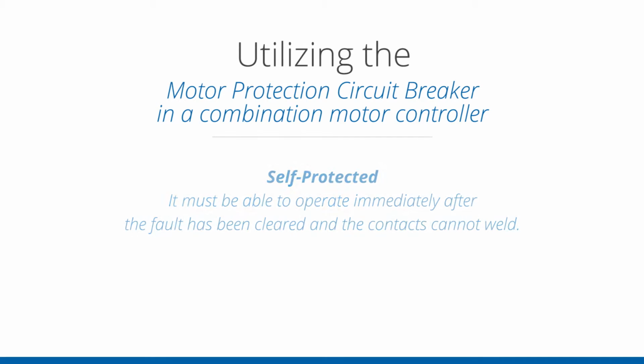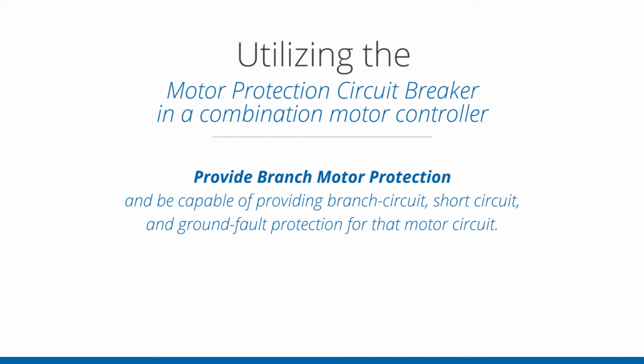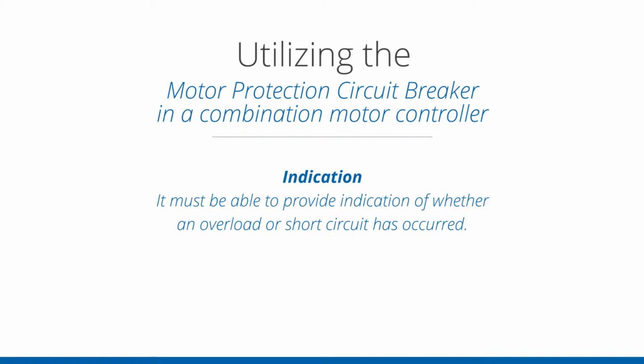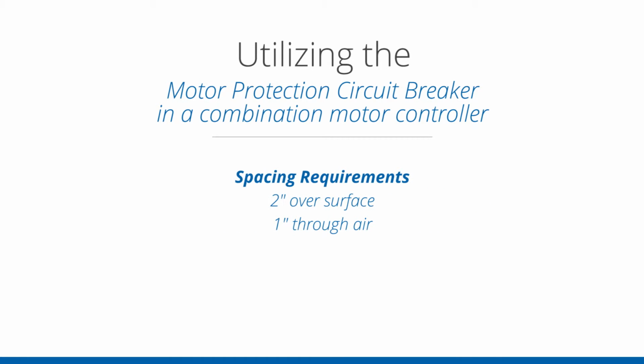First and foremost, it must be self-protected, indicating it must be able to operate immediately after a fault has been cleared and the contacts cannot weld. It must provide branch motor protection and be capable of providing branch circuit, short circuit, and ground fault protection for that motor circuit. It must be able to provide indication of whether an overload or short circuit has occurred. And it must meet larger minimum spacing requirements as a branch device, meeting 2 inches over surface and 1 inch through air, and this installs on the line side of the motor protection circuit breaker, compared to the standard industrial control equipment, 3/8 inches over surface and 1/2 inch through air.